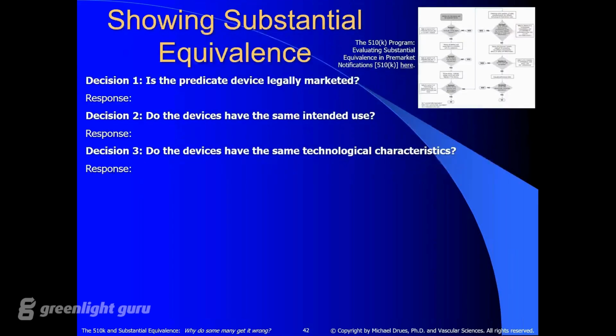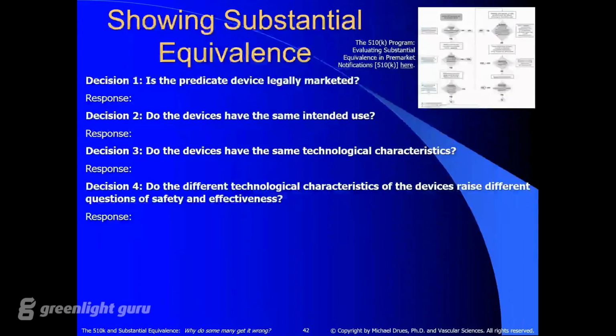So once again, I take the exact same approach. I create a technology matrix, and for the technologies that are the same, I highlight those in green. For the technological characteristics that are different, I highlight those in red, and for the ones that are in between, I highlight those in yellow. So the regulatory logic on both the labeling as well as on the technology side is exactly the same. Of those technological differences that do exist compared to the predicate, do they raise additional questions of safety and effectiveness? And once again, we have to respond to that. Just because they do does not necessarily kick you out of the 510K, but you do have to address them.